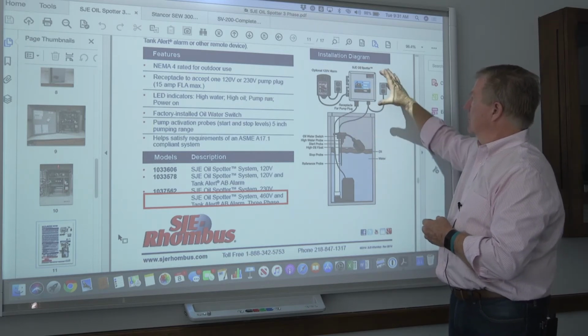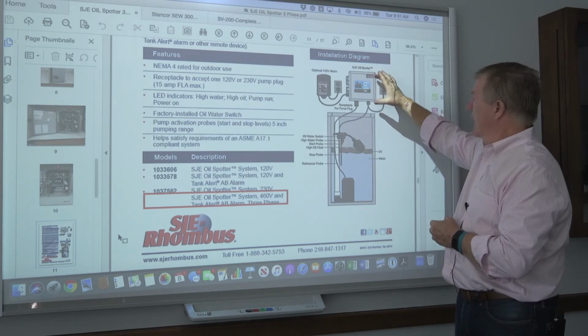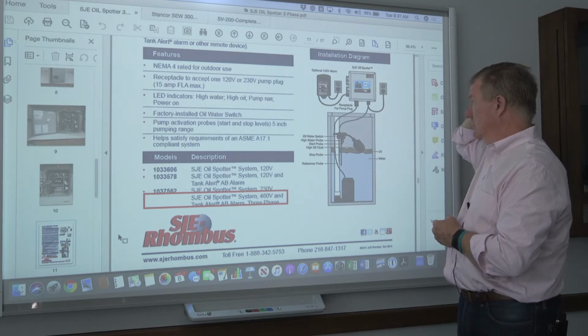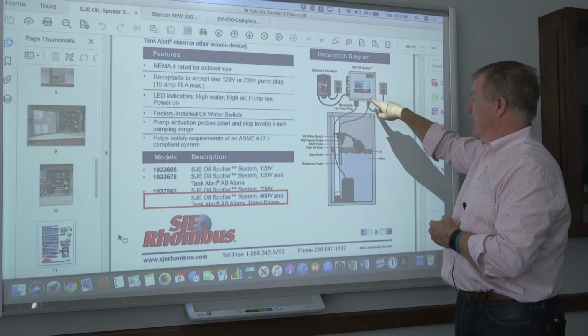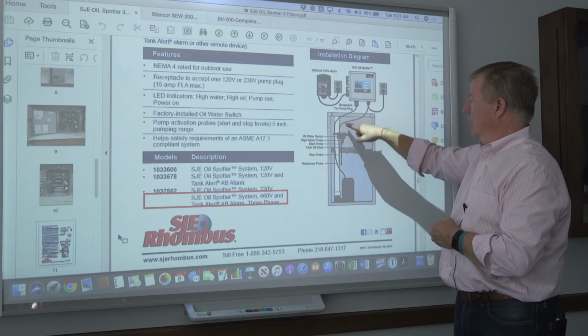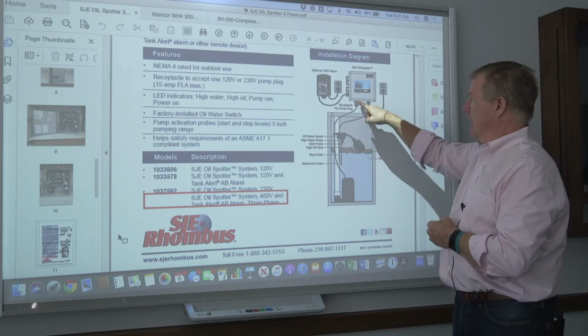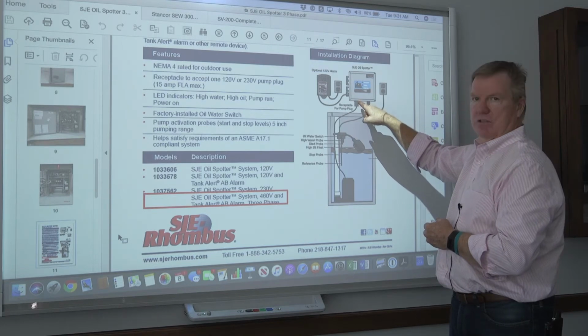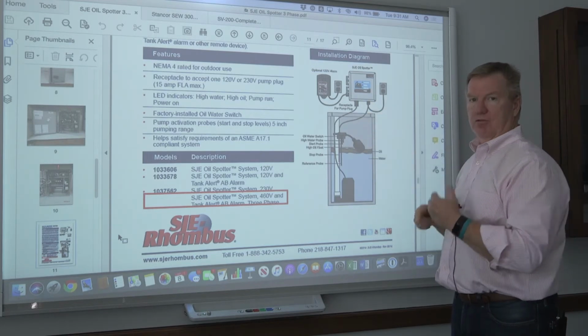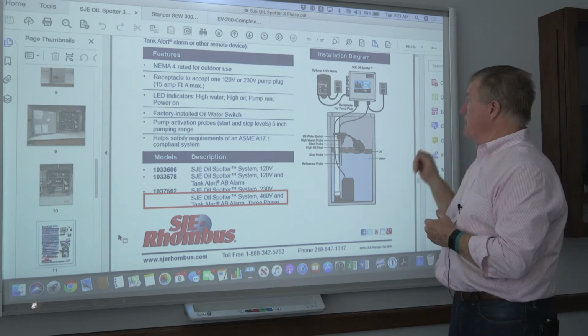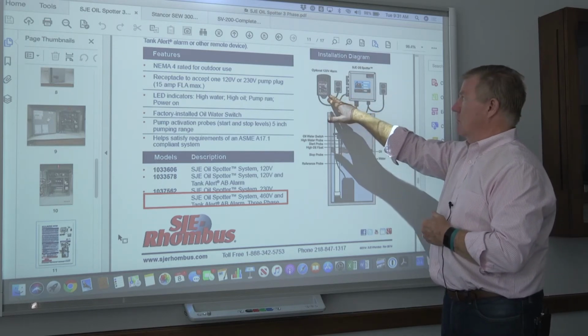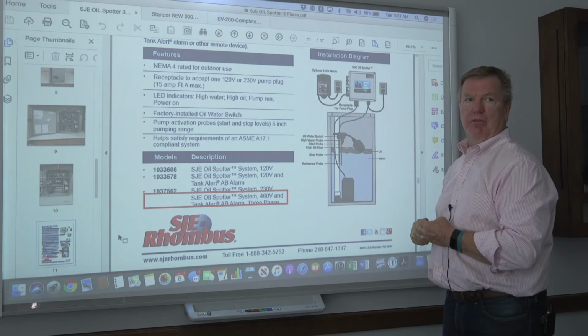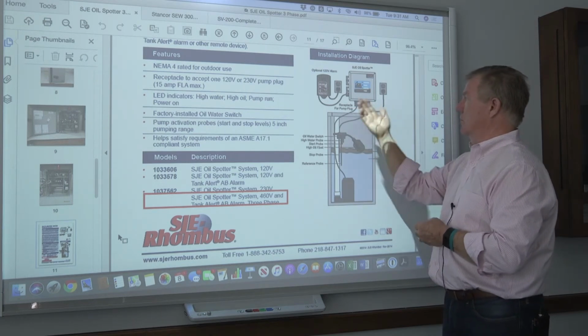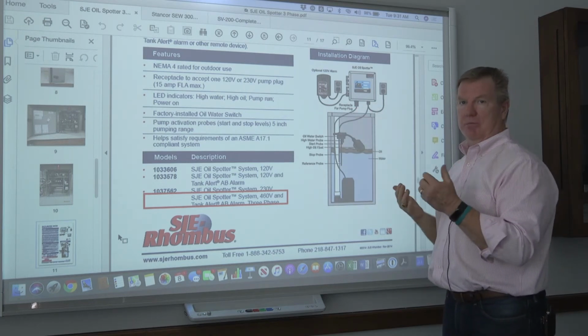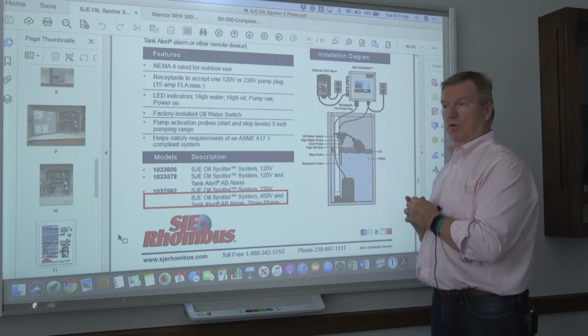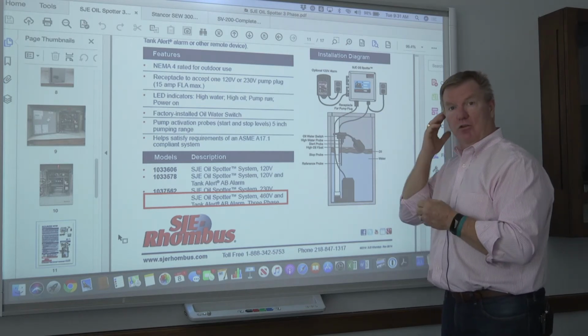This is our control panel that we were just looking at, that's powered, plugged in. And then out of that, we have both the power cord that goes down to the pump, and then we have the float system that goes into the sump for turning the pumps on and off. There's an optional alarm that can be provided with this sump also. So if you have any of the alarms, those alarms can be either a horn or a dry contact to go to another part of the building.